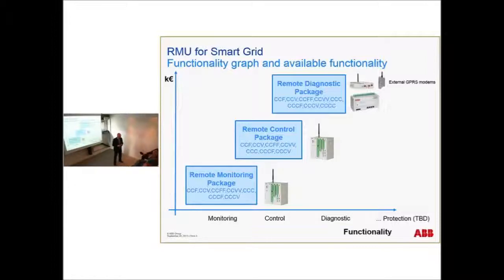One more question. The SF6 breakers. You're monitoring the SF6. Is it in such a way that if there's a leakage and it comes to a certain level, you get a warning, and further down it is blocked? What we monitor is the pressure, because the unit is filled with 1.4 bar.